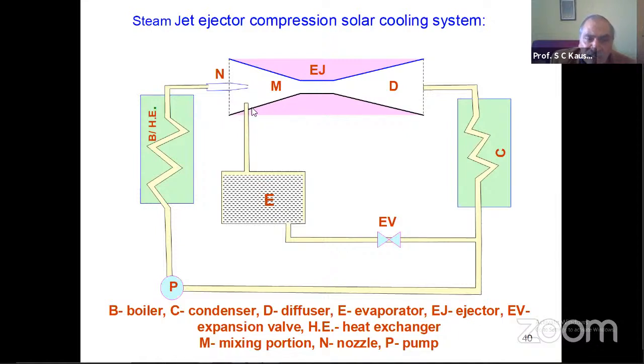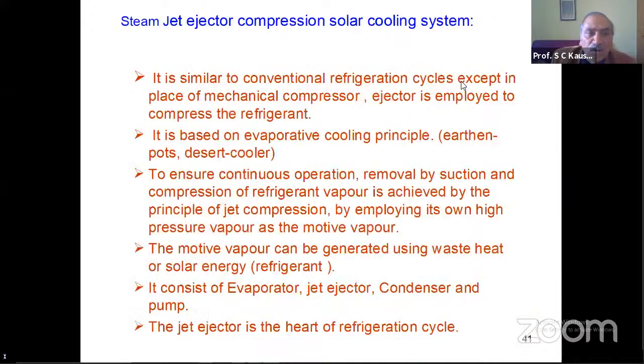So by providing this, we may have some heat engine coupled with the vapor compression cycle, say evaporator, condenser, expansion valve, and this compressor. The overall efficiency is okay, and this system is simple in design as compared to the Rankine cycle cooling system. The jet ejector is the main part of the refrigeration cycle, and the evaporative cooling principle is used in this jet ejector cooling system.